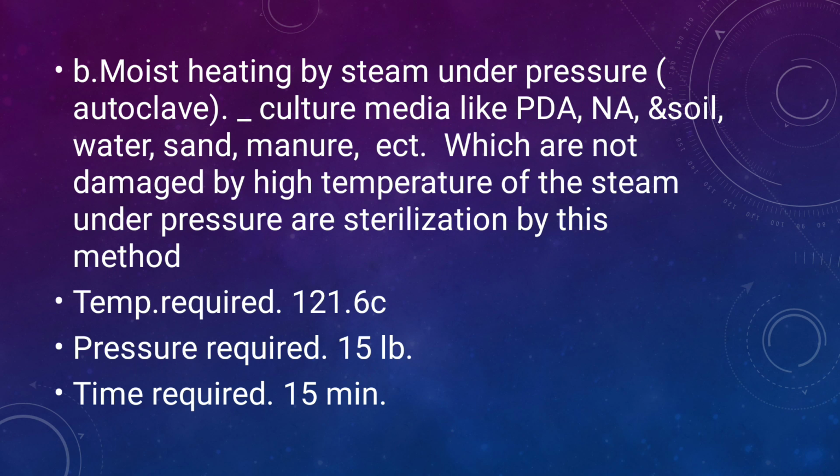The pressure required for the sterilization is 15 lbs per square inch, or psi, and the time required for the sterilization is 15 minutes. That means within 15 minutes, the temperature reaches up to 121 degrees Celsius, and the pressure involved here is 15 lbs.